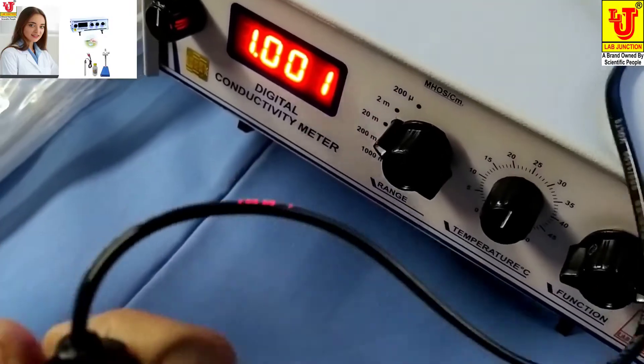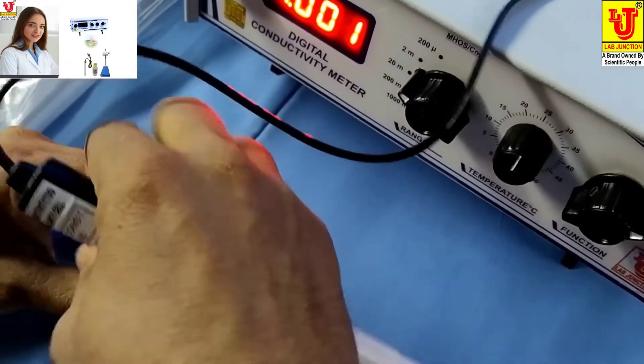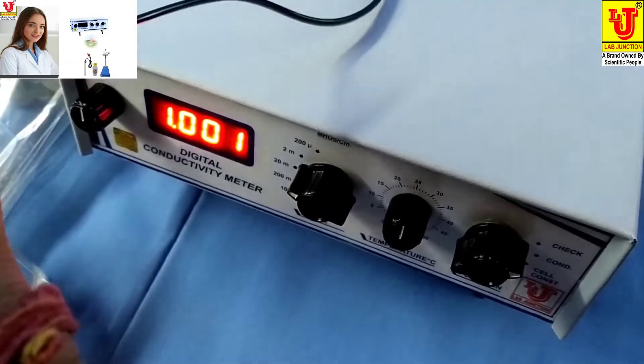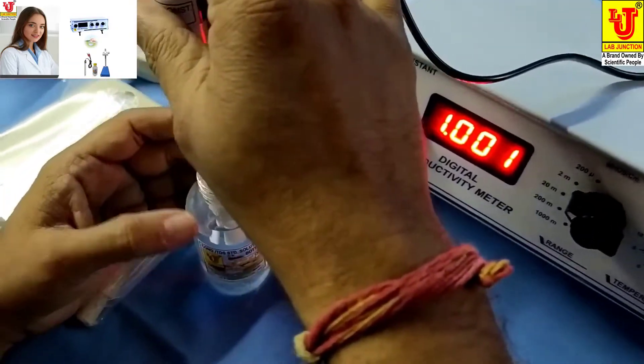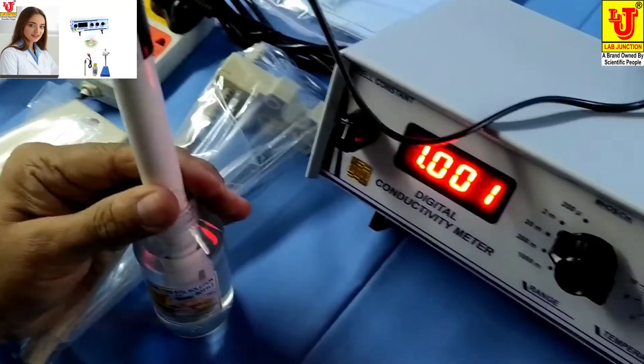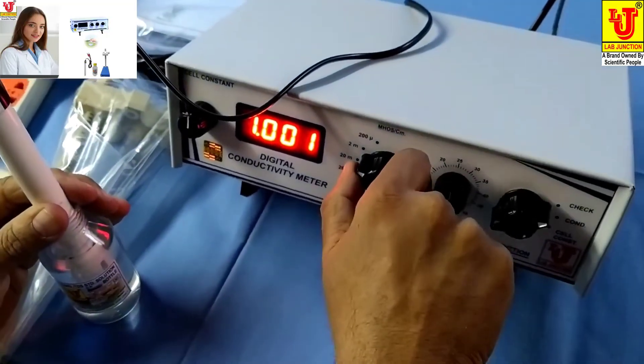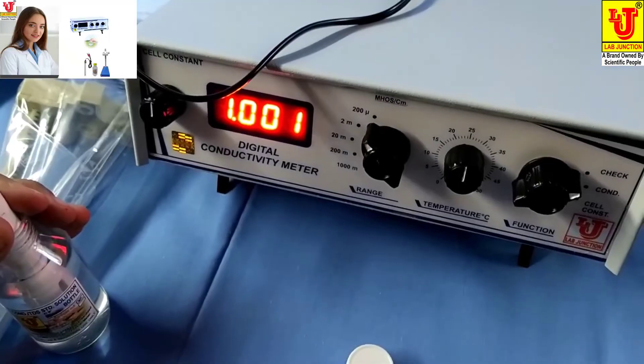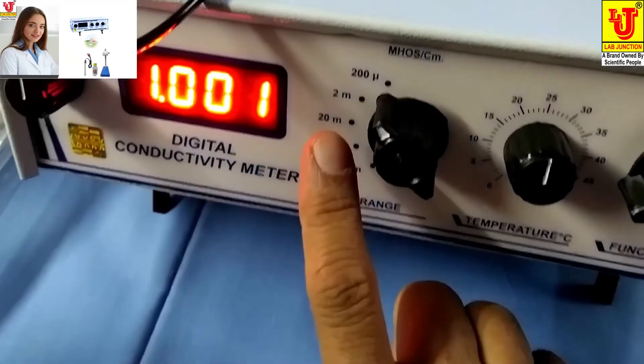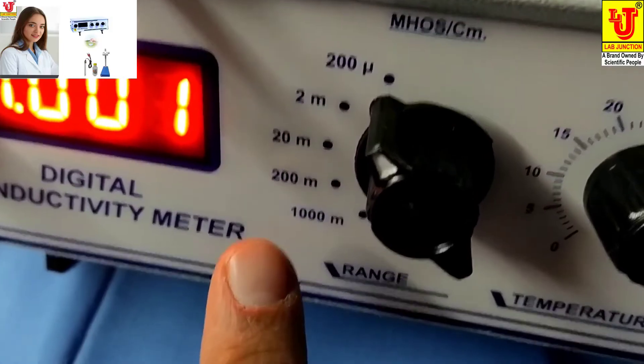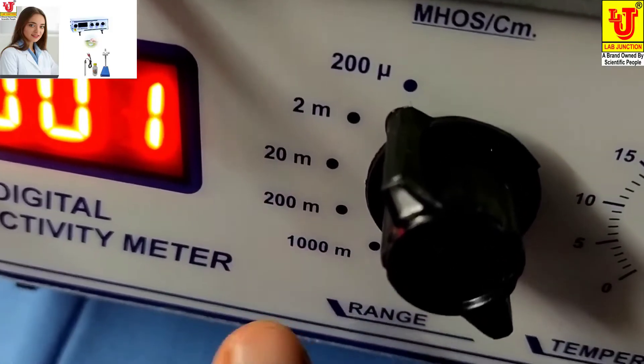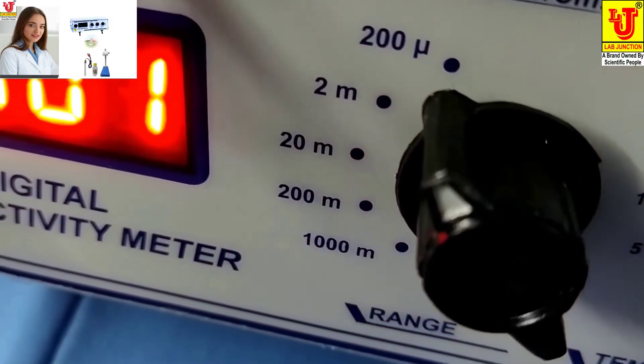This is our conductivity solution. You can dip in that. And you can set first range, 200 microsiemens, second is 2 milli, third is 20 milli, fourth is 200 milli, fifth is 1000 millisiemens.